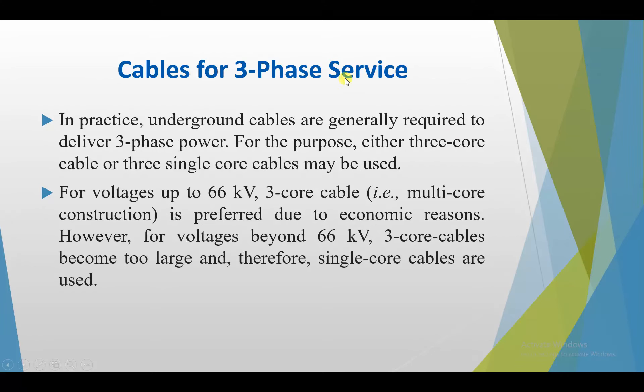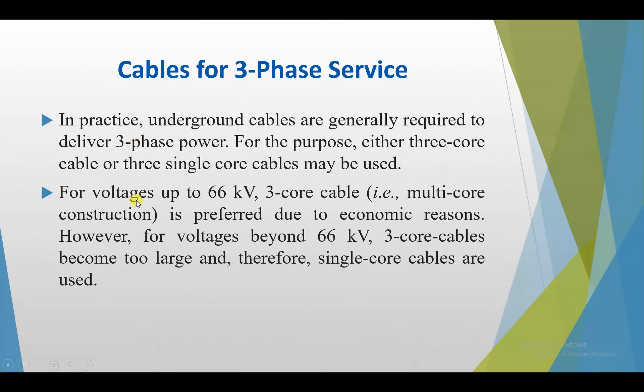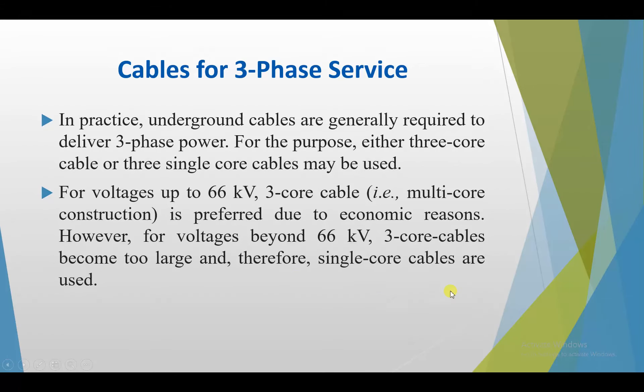For cable for three-phase service: in practice, for distribution purposes, underground cables are generally required to deliver three-phase power. For this purpose, either three-core cable or three single-core cables may be used. For voltages up to 66 kV, three-core cable — that is multi-core construction — is preferred due to economic reasons.